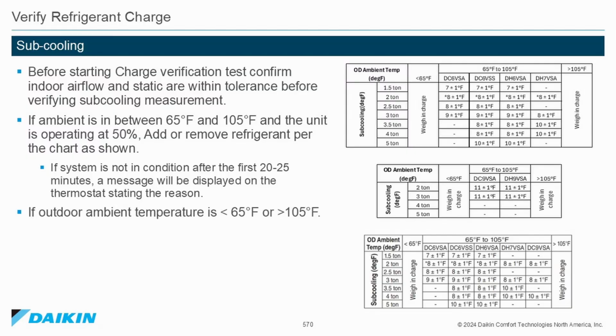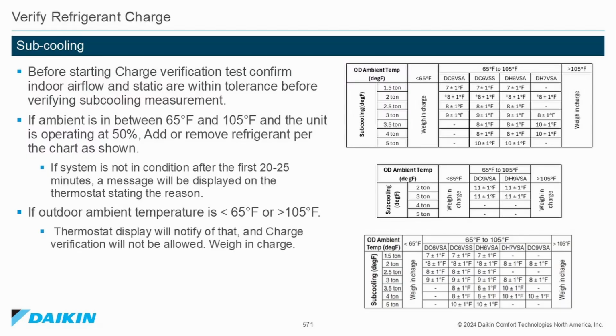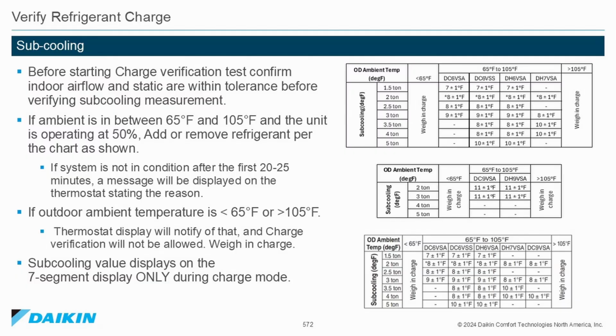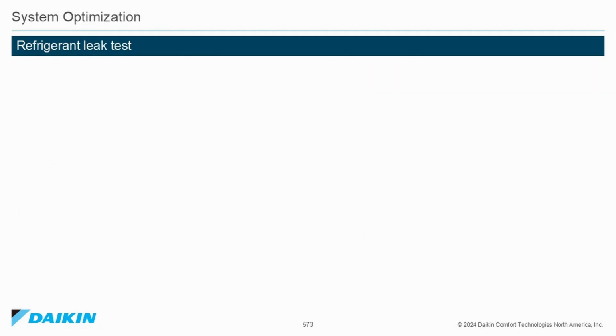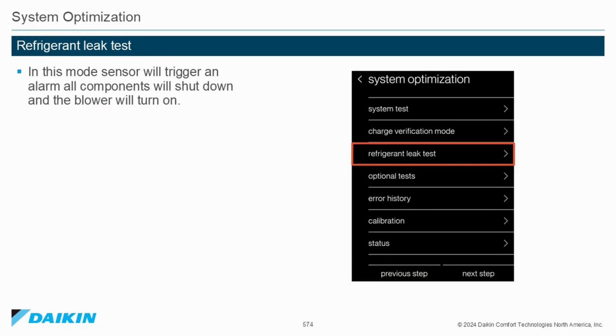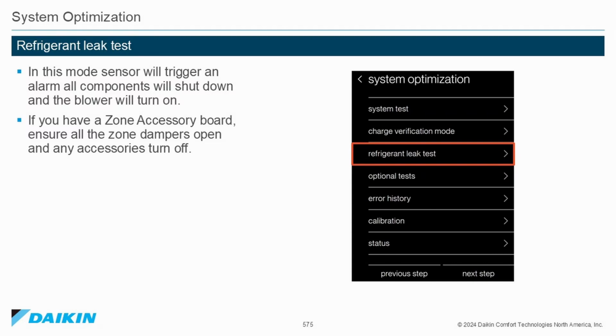If the outdoor ambient temperature is less than 65 degrees Fahrenheit or more than 105 degrees Fahrenheit, thermostat display will notify you of that, and charge verification will not be allowed. Weigh in the charge. Subcooling value displays on the 7-segment display only during the charge mode. System optimization. Refrigerant leak test. In this mode, the sensor will trigger an alarm, all components will shut down, and the blower will turn on. If you have a zone accessory board, ensure that all zone dampers open and any accessories turn off.